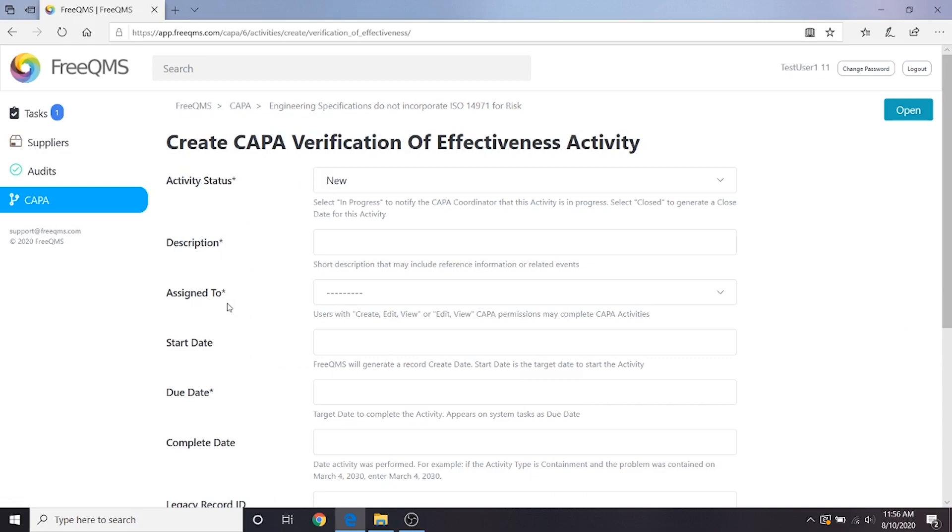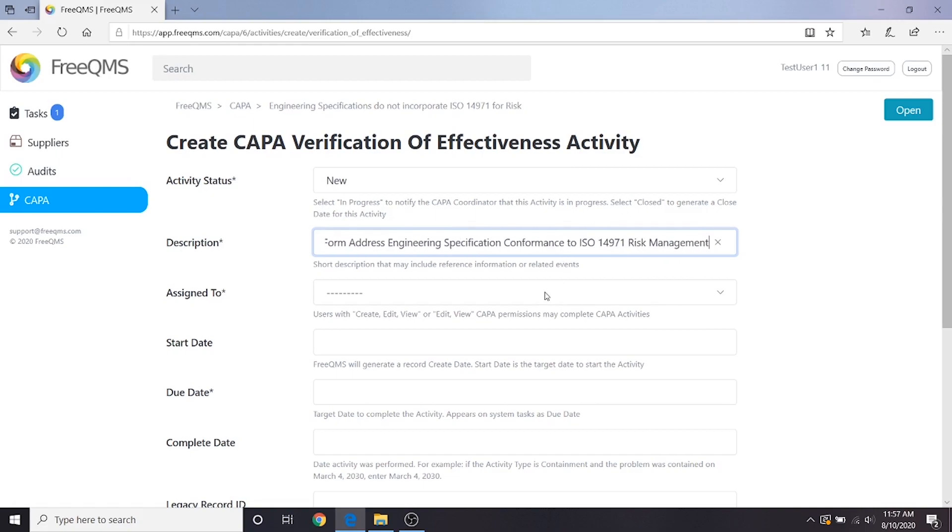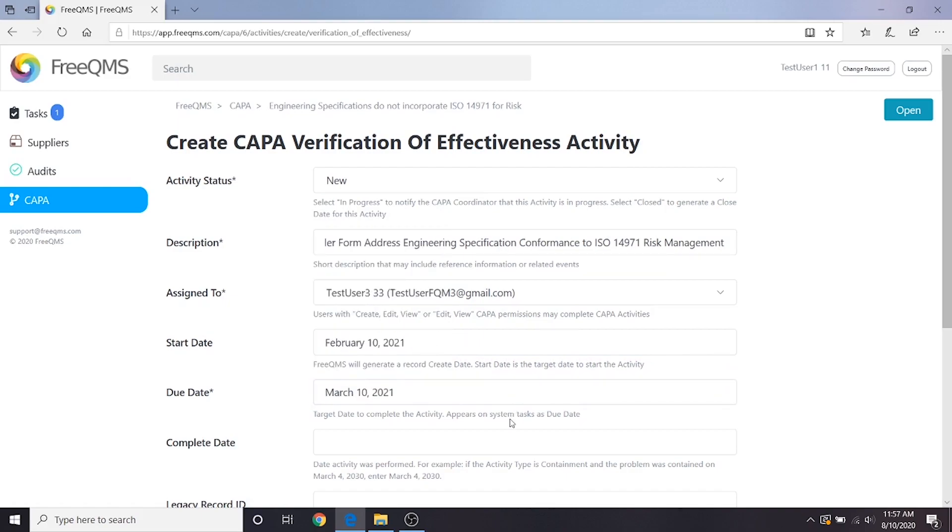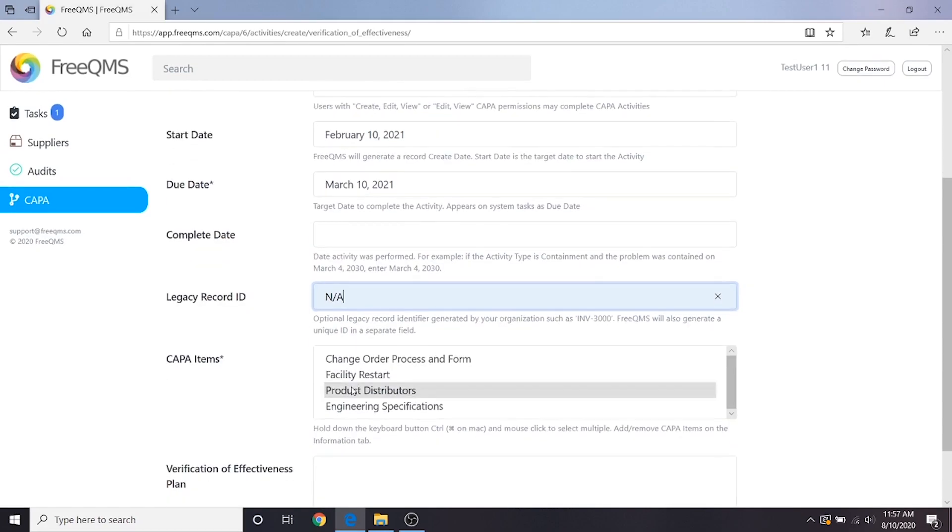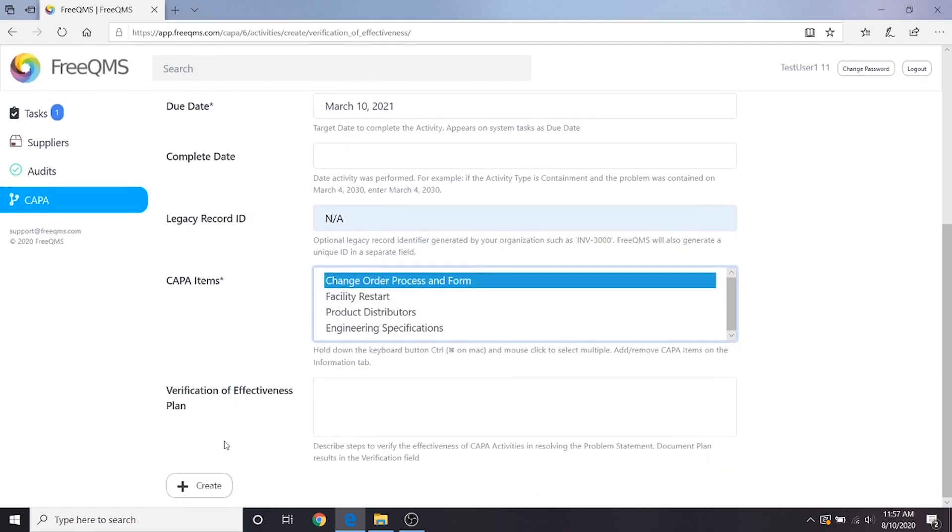Now we have our corrective action created but there's one step left. We need to make sure we're correct and the only way to do that is through verification of effectiveness. The verification of effectiveness activity, commonly abbreviated VOE, is meant to serve as a long term quality check on our work. Let's click the create CAPA activity button and then verification of effectiveness. Once again, the activity form is the same except the final fields. Activity status, new. Verify updates to change order form or address engineering specification conformance to ISO 14971 risk management. Assigned to user 3, the quality specialist. Start date 6 months from now. Due date 7 months from now. Complete date is unknown. Legacy record ID is NA. CAPA items, change order process and form. Verification of effectiveness plan will be completed by user 3. Let's click create.